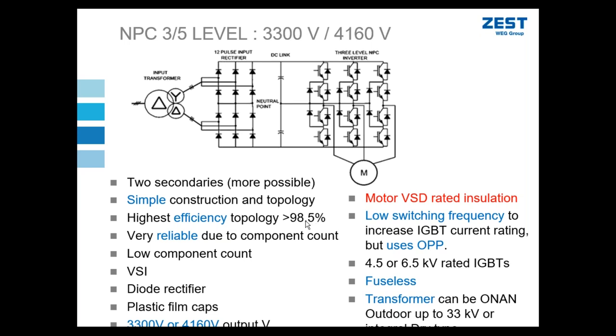When you're talking medium voltage drives, you're often talking in the large megawatt ranges. Efficiency differences of 0.5% to 1% can make a dramatic difference to long-term costs, but also arguably more importantly, to the heat losses emitted into a substation. This topology is very reliable because its component count is the lowest of the MV topologies available.